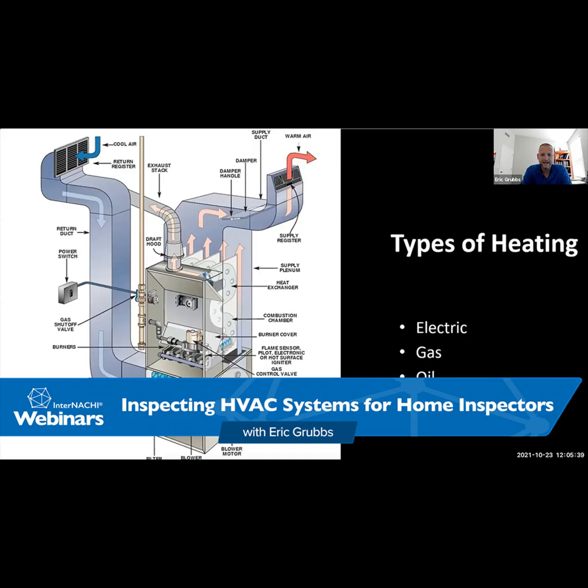So from a manufacturer standpoint, heat exchangers typically come with a 20-year warranty in case anything ever happens to that heat exchanger. These furnaces are way over that 20-year period. So one, they're not under warranty. Two, you do risk the expansion and contraction of that metal over that period of time causing multiple issues with those types of furnaces. It's just way better to replace those, or at least put the recommendation in for replacement. And if they don't have carbon monoxide testers, I would definitely not operate it without a carbon monoxide tester, just in case there is a cracked heat exchanger.